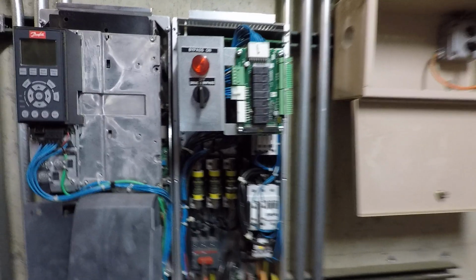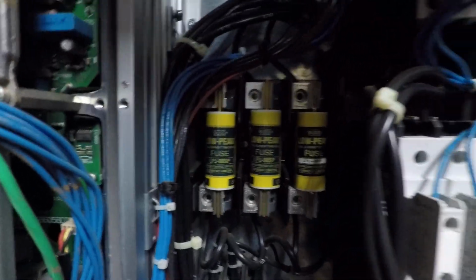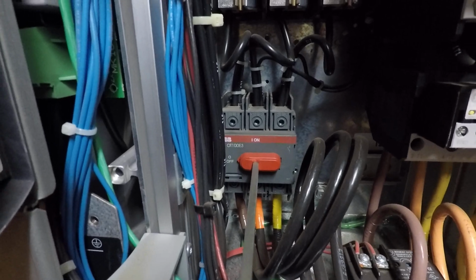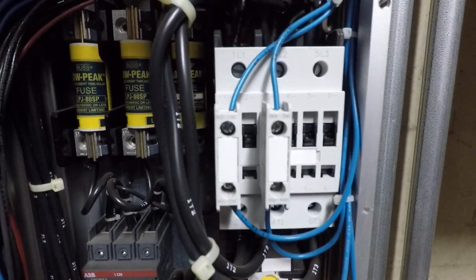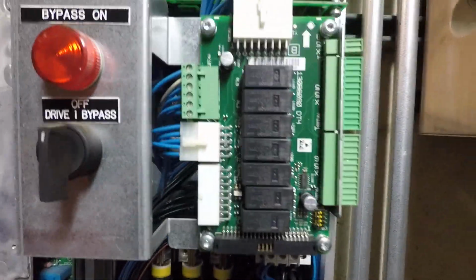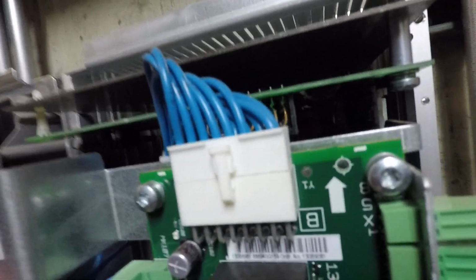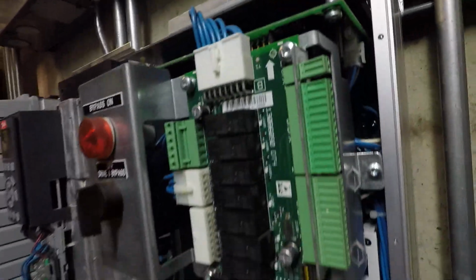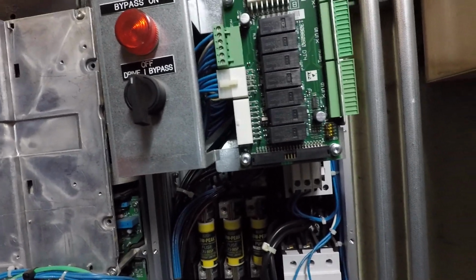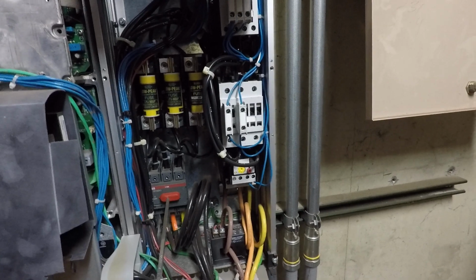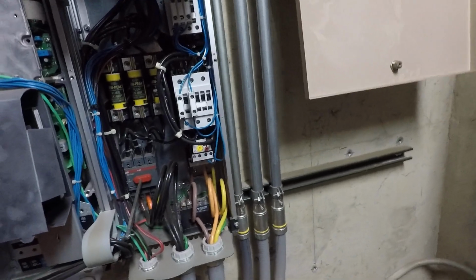And then the bypass section over here, we've got the incoming line fuses, we've got the disconnect, we've got a contactor for the bypass, overload relay, contactor for the drive, a relay board, and up here this horizontal board has a 24 volt power supply built into it that only provides enough power to operate what's contained in the drive. So you can't use any of this power for external devices like EPs or other relays or what have you.